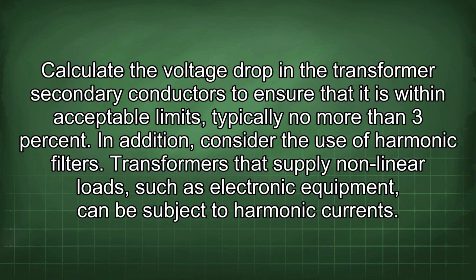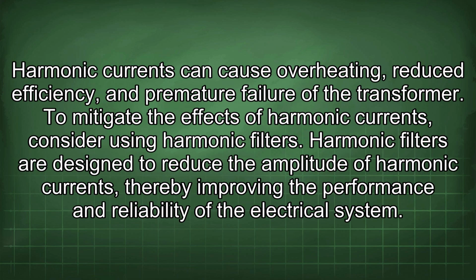Transformers that supply nonlinear loads, such as electronic equipment, can be subject to harmonic currents. Harmonic currents can cause overheating, reduced efficiency, and premature failure of the transformer. To mitigate the effects of harmonic currents, consider using harmonic filters.